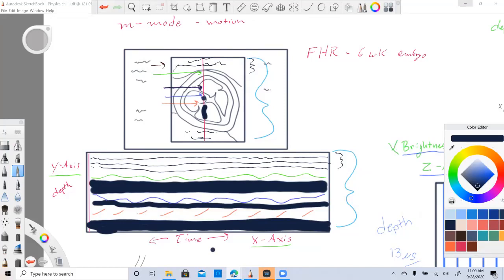So the mechanical index for M mode is actually a little bit higher than grayscale alone. We really don't talk about mechanical index for a while, but I just want to mention this. So color Doppler on a 6-week, let me draw a little 6-week embryo. There it is. Color Doppler, don't do it.